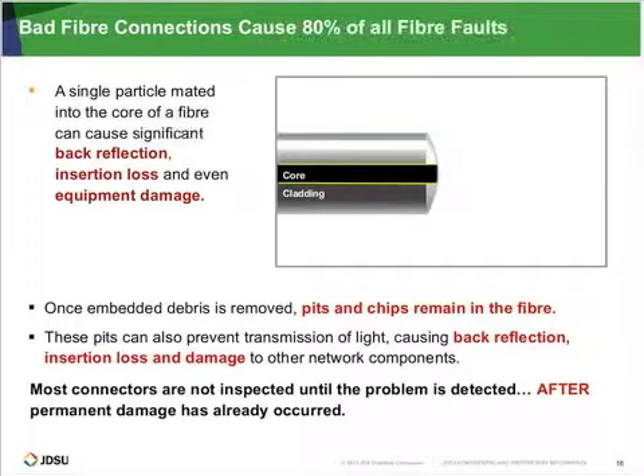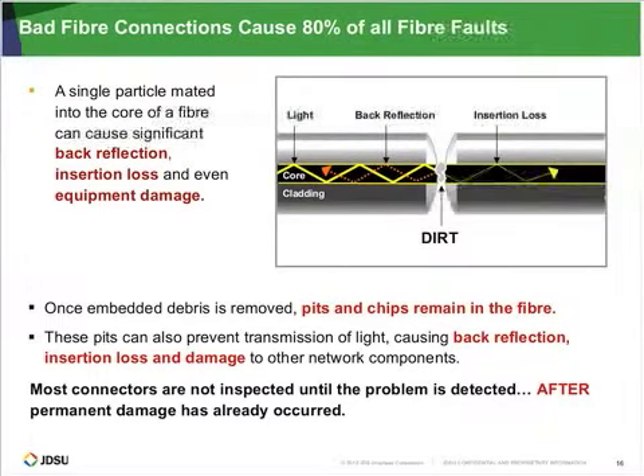With single mode fiber, even a single particle on the core of the fiber matters. The core of single mode fiber is 9 microns, while a typical piece of dirt is around 4 to 6 microns, so it's a very large part of the core. Even a single particle on the core causes back reflection, which can destabilize the lasers, cause insertion loss, and damage the connector. The light that's reflected doesn't go through to the other connector and will cause loss in the link.